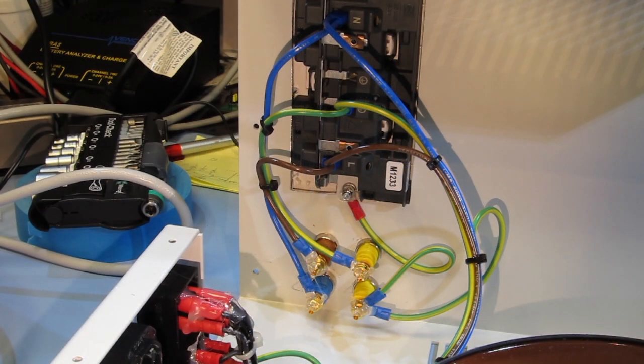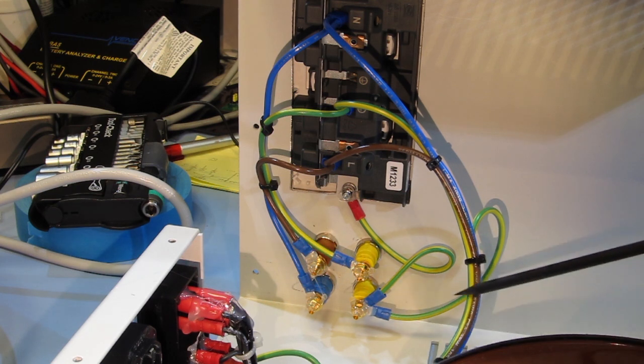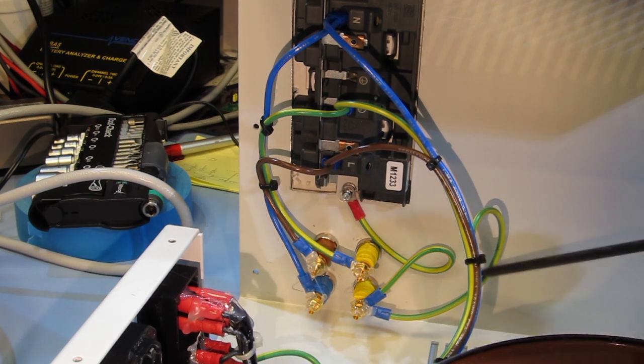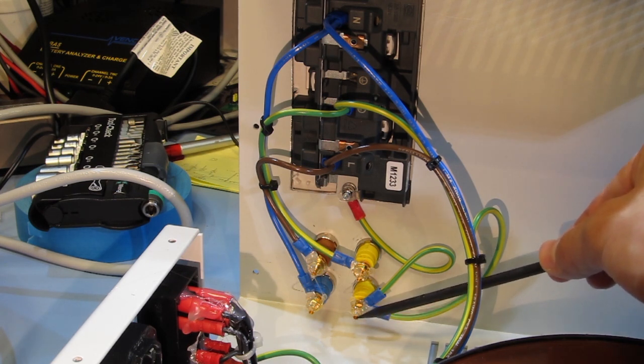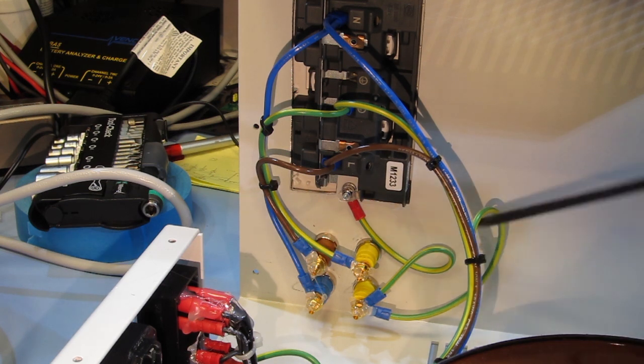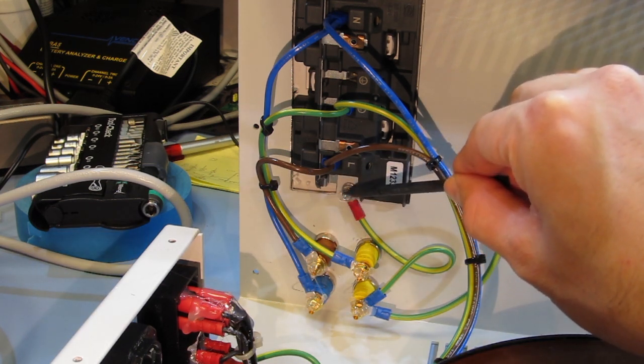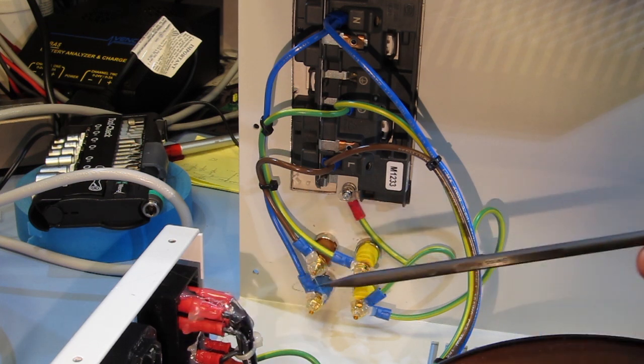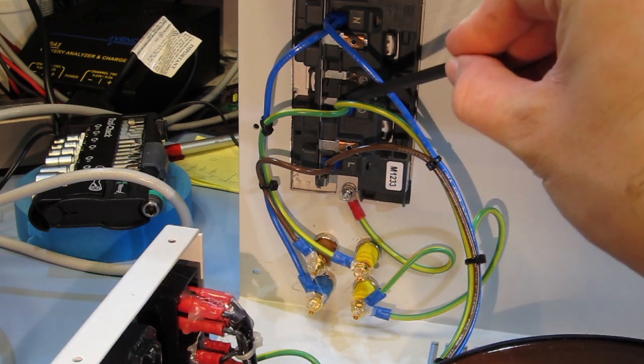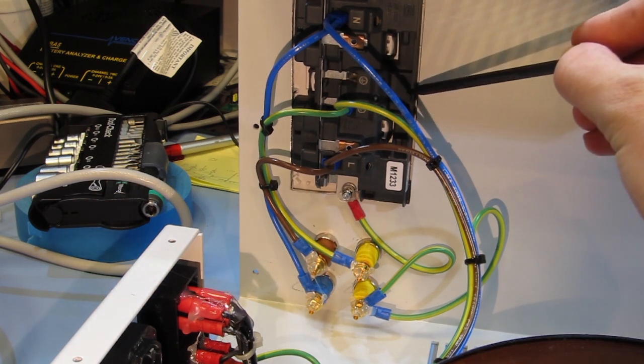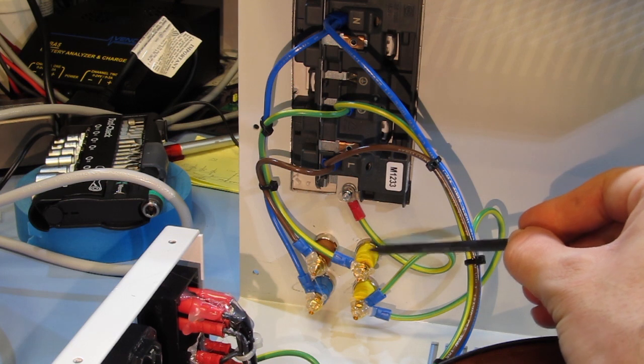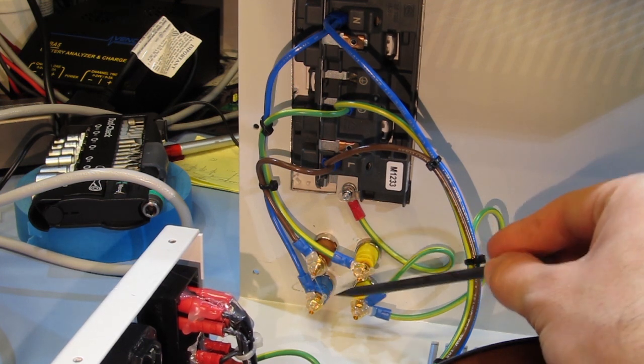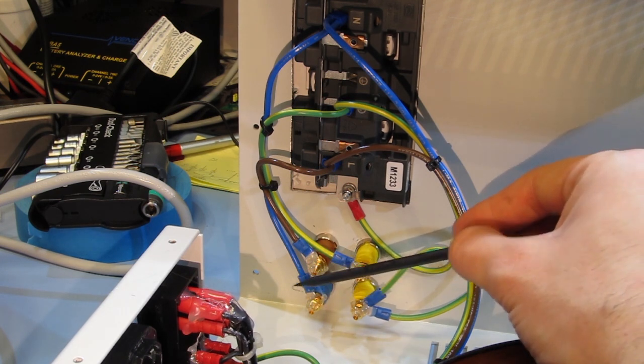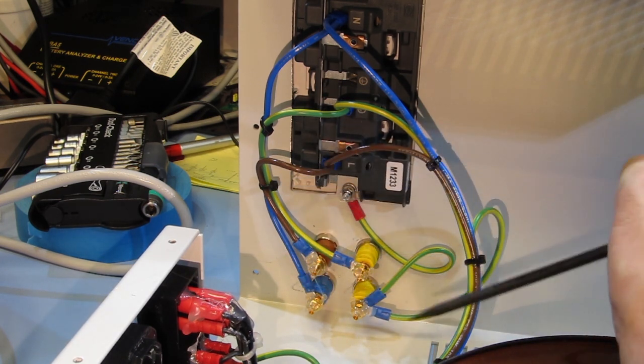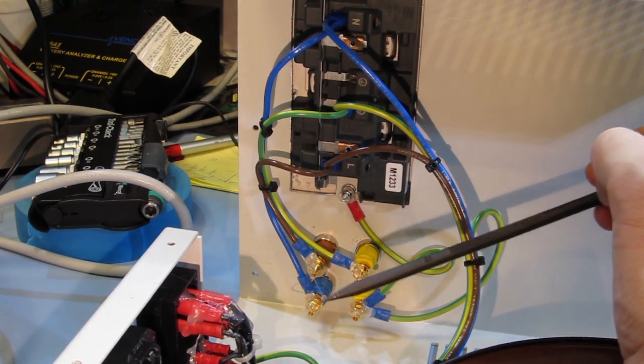Now as we move on to the top cover, we've got our bundle of wires coming up along here. We have our mains earth connected to the banana plug at the bottom here, the earth one here, and that's also looped round and connected to the chassis on the top. We also have our earth, which comes only from the outlet IEC connectors, which connects to the earth on the socket at the top, and that then only goes to this banana plug on the top here. And then finally we have our two outputs from the transformer, which are looped into the 13 amp socket, and those are the ones connected to the IEC connectors on the front panel.